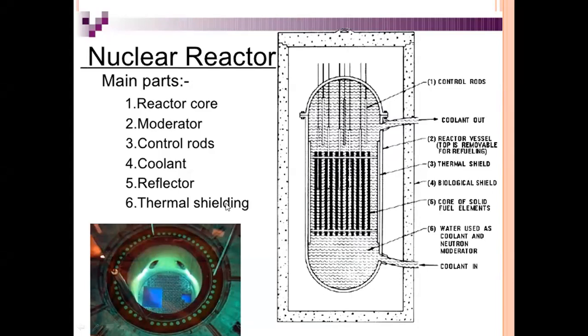So, the main parts of a reactor are the reactor core, moderator, control rods, coolant, reflector, and thermal shielding. See here, this is the control rod. Coolant out from here, reactor vessel outside, thermal shield here, biological shield outside. The core is a solid fuel element, water is used as a coolant and neutron moderator, and this is coolant in, like that.